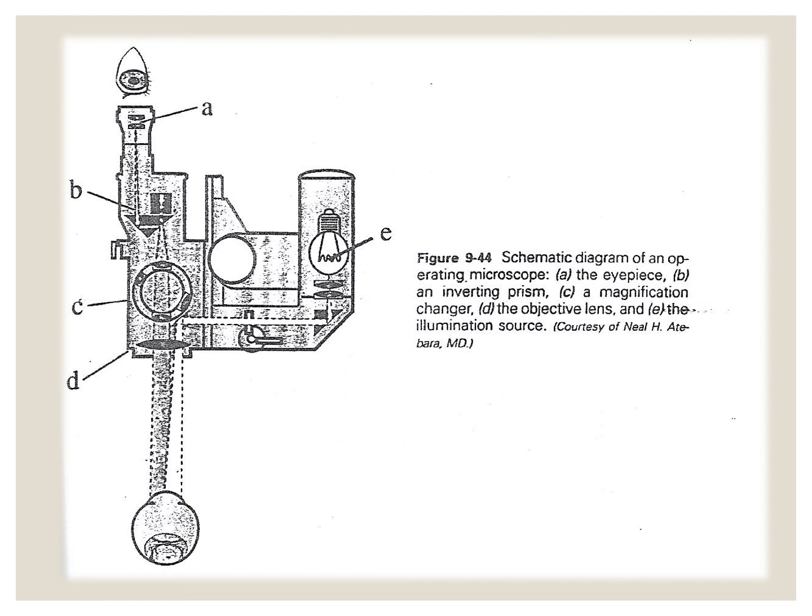This image has to be rectified by a pair of porro prisms, then further magnified again by the magnification changer, which has the optical principle of a Galilean telescope, to finally pass the image through the objective lens. The objective lens here faces the eye of the patient.